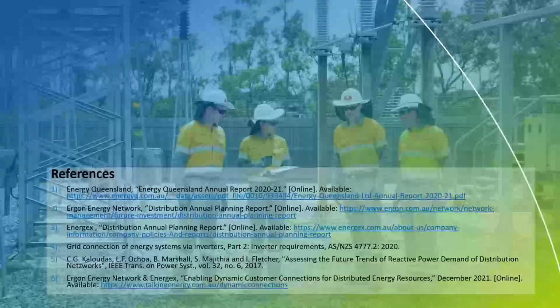That's another good question. I can't confirm where it's coming from, but I can confirm these changes in reactive demand have been seen internationally. One reference is from the UK, where they've seen similar things over the last decade. That suggests at least part of it relates to the change in the types of loads customers have. I'd suggest there are a lot more power electronic loads. Most appliances these days have inverter front ends, which probably give a very good power factor, unlike old inductive motors.